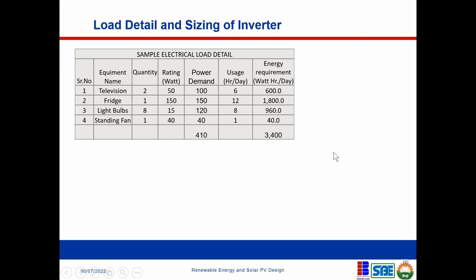But what if you didn't do your calculation very well, and that load actually requires maybe 4 kilowatt hour? It means that you have under-designed that system as well. Because before it gets to the 6 hours that the load needs to run, the battery will have drained and the load will be shut off.